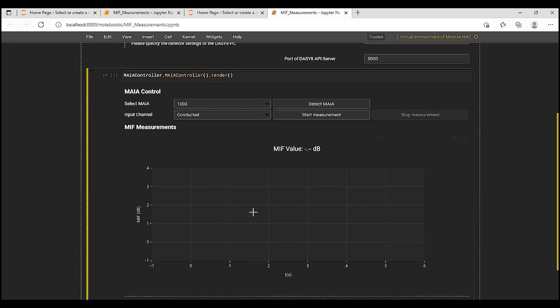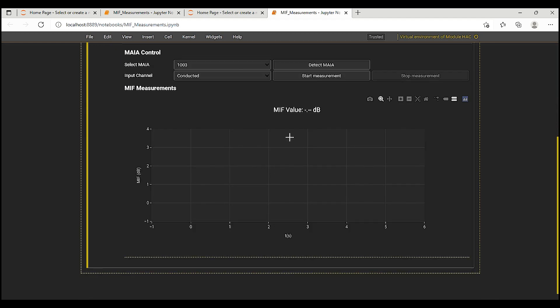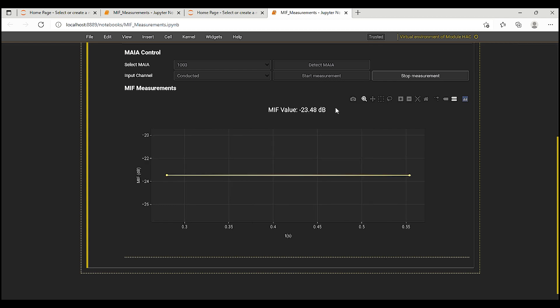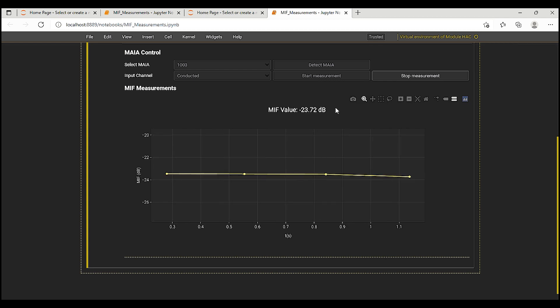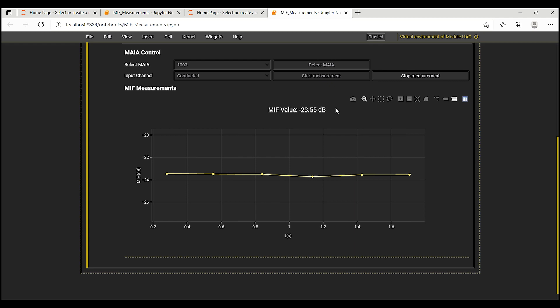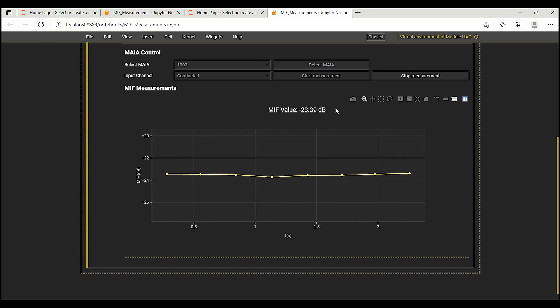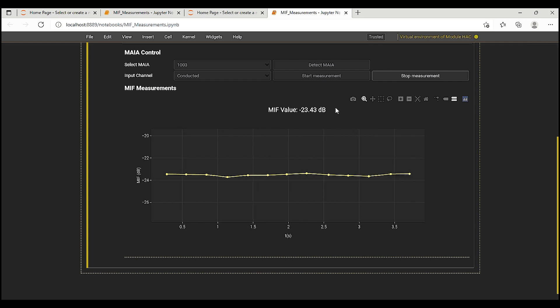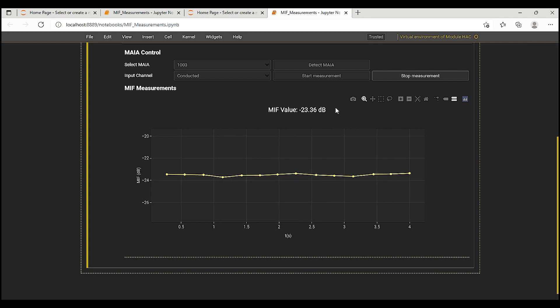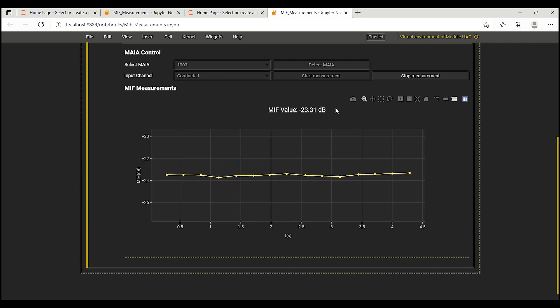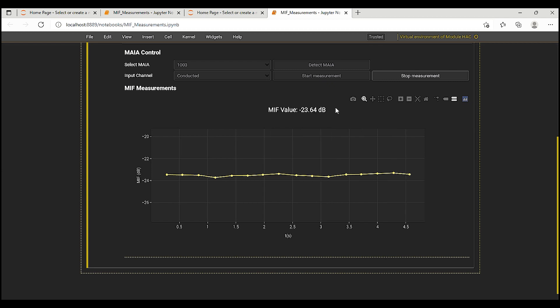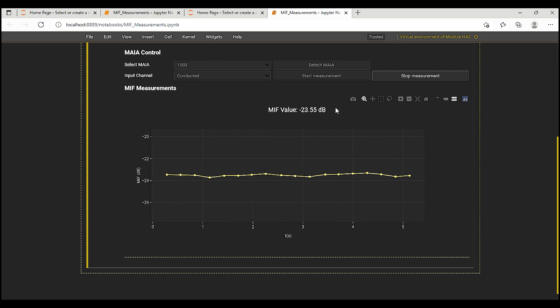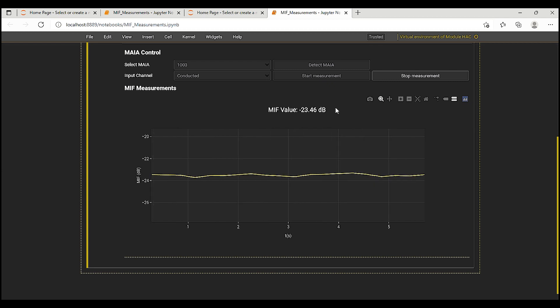Then, I start the MAIA measurement. So, the MAIA reports a MIF value of -23.56 dB. I compare this value to that given by SPYAD in the communication systems database on their website, which is -23.48 dB. The difference is well within the combined uncertainty of the two measurements.